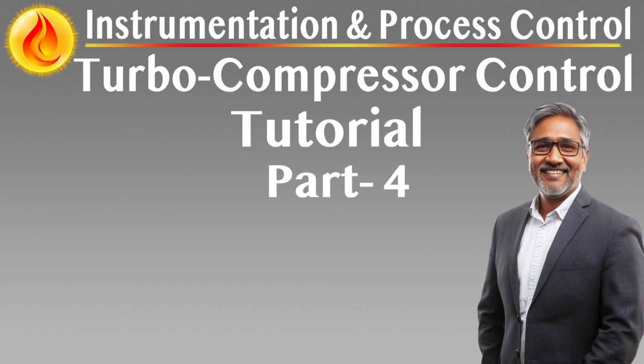Application software development. The vendor develops and delivers fully functional software covering startup and shutdown sequences, protection and interlocks, controller algorithms, e.g. PID surge performance, HMI navigation and displays, communication drivers to DCS, ESD, MCC, and CMS. Documentation deliverables. The vendor provides detailed logic diagrams and tag references, configuration files in native and export formats, I/O point-to-function mapping, controller configuration reports, software architecture overviews. Code transparency. All programming must be human-readable, even for proprietary systems, ensuring maintainability by the owner post-commissioning.